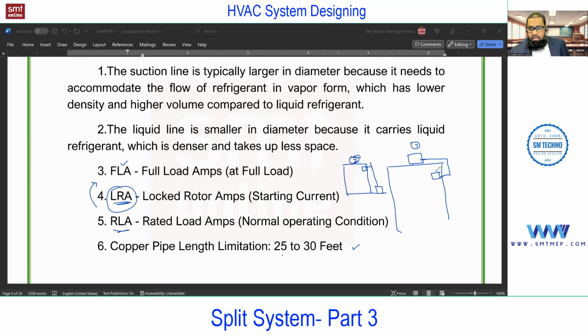So if you place them on a similar level, for example, just above that floor if you place the outdoor, we can maintain the length up to say 15 meters, meaning 30 up to 45 feet. And in this case, we can go for 15 feet. And if the outdoor is on the top and the indoor at the bottom, we can consider nearly 20 feet. So this is approximate, and the exact figure you can get from the vendor.